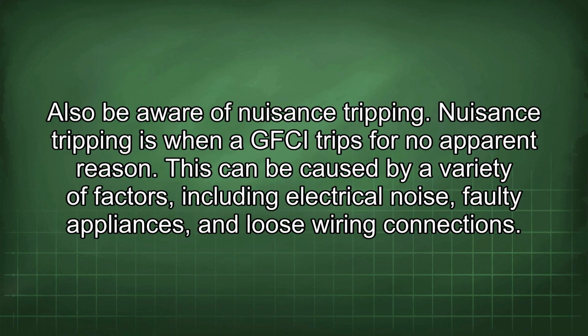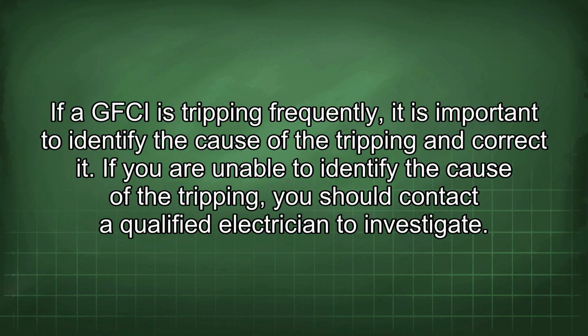Also be aware of nuisance tripping. Nuisance tripping is when a GFCI trips for no apparent reason. This can be caused by a variety of factors, including electrical noise, faulty appliances, and loose wiring connections. If a GFCI is tripping frequently, it is important to identify the cause of the tripping and correct it. If you are unable to identify the cause of the tripping, you should contact a qualified electrician to investigate.